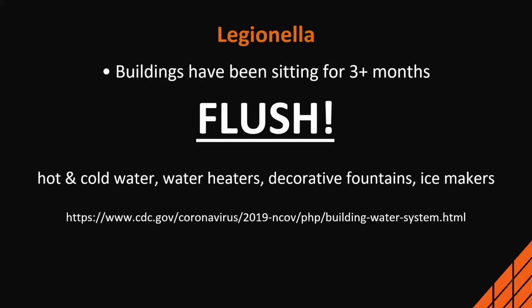This link here from the CDC describes how to flush them. And you got to be really careful as you go back into buildings that they are flushed properly, and as you go back into floors. So if the building's been occupied, but floors 2 through 8 haven't, then you have to flush each of those floors, and watch out for long runs to things like ice makers, which have very low flow rates, to make sure that they're flushed out properly.